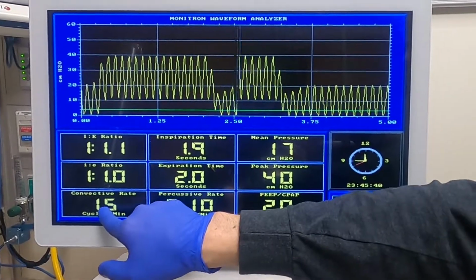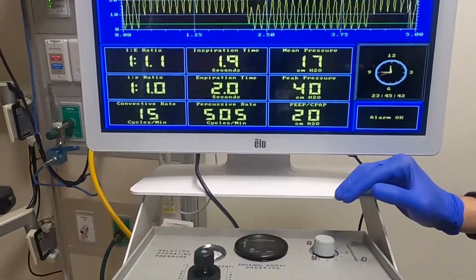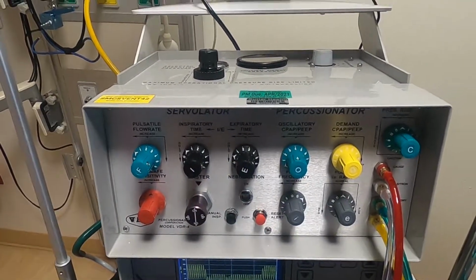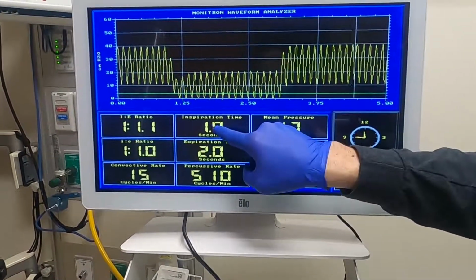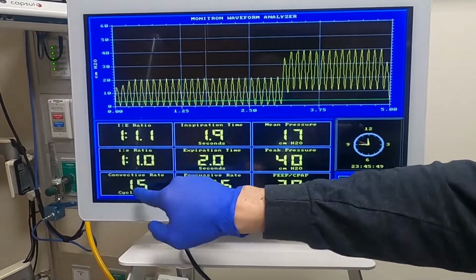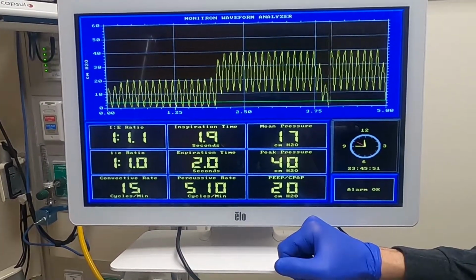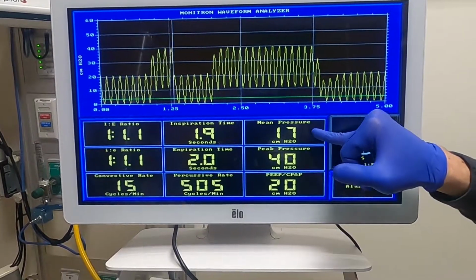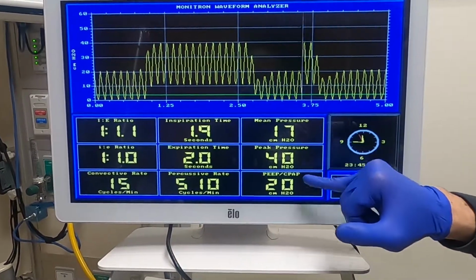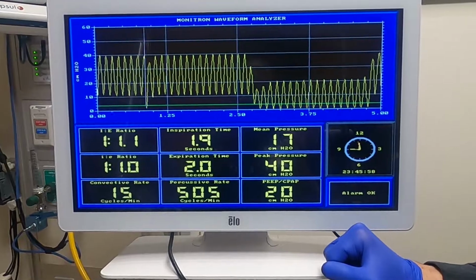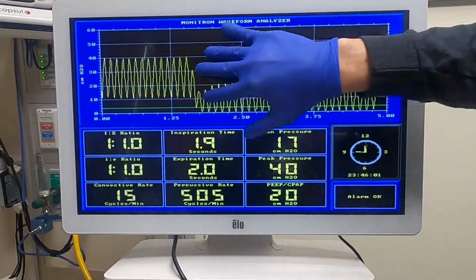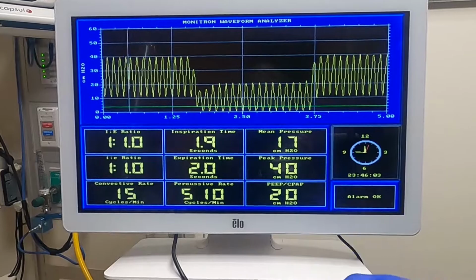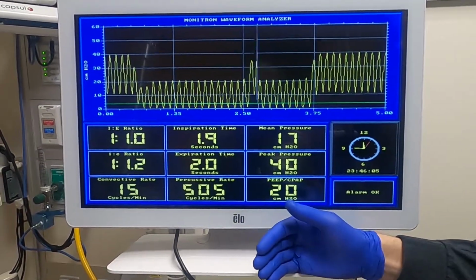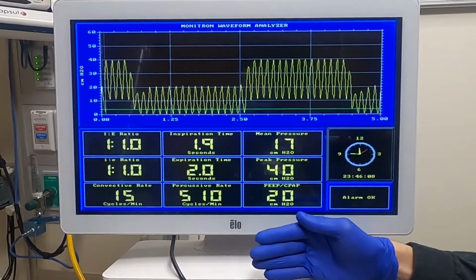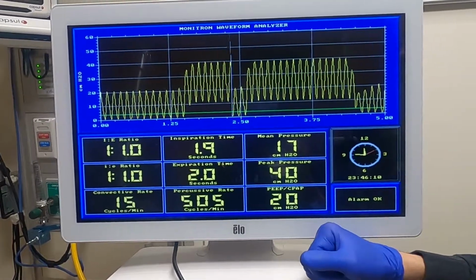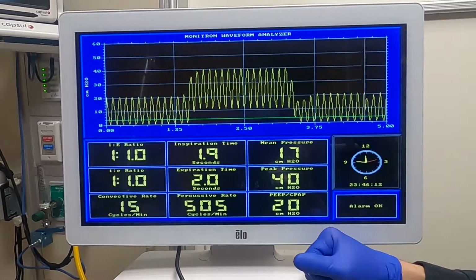For our convective rate, we're going to set it here. And we're going to, for the most part, use a 1-to-1 IE ratio. So 2 and 2, it's a rate of 15. There's some other, here's your mean airway pressure, peak pressures, your CPAP. This is a really important thing. It can tell you a lot about what's going on with the patient. Is your circuit set up correctly? Do they need to be suctioned? Is there a big air leak? The waveforms can tell you a lot about that.